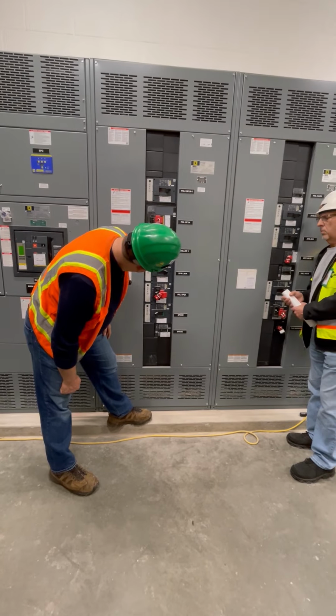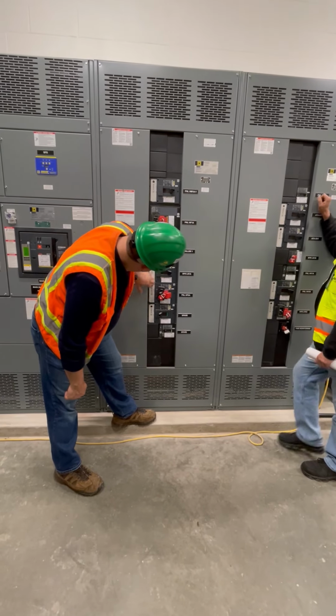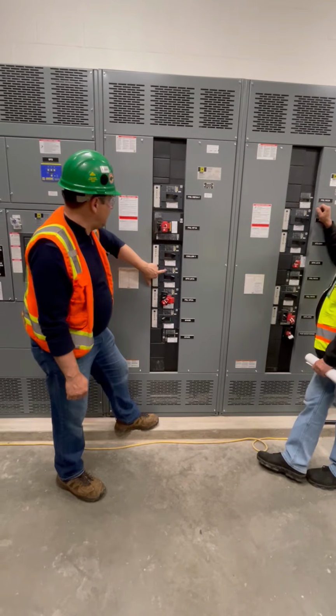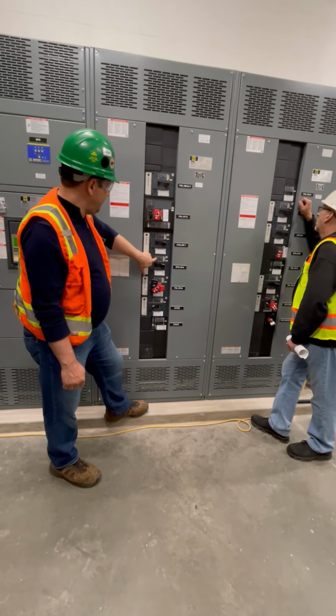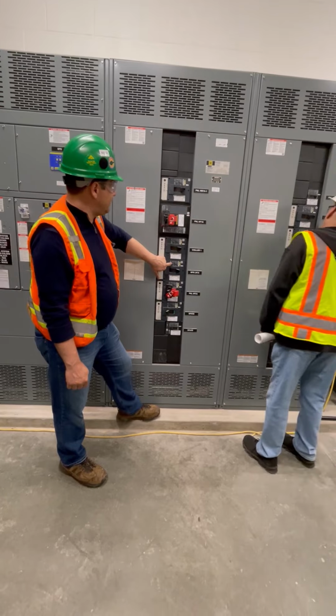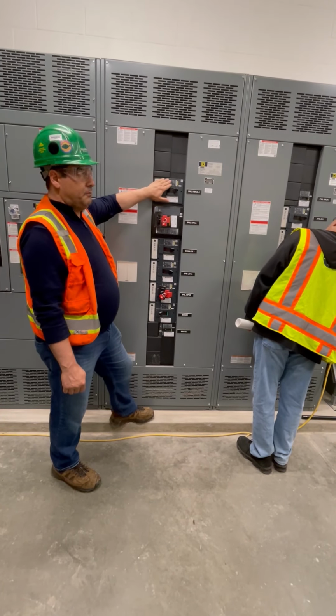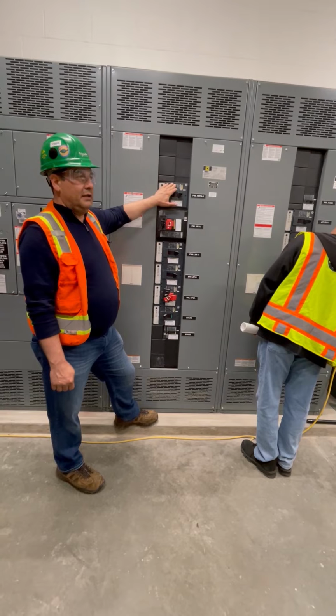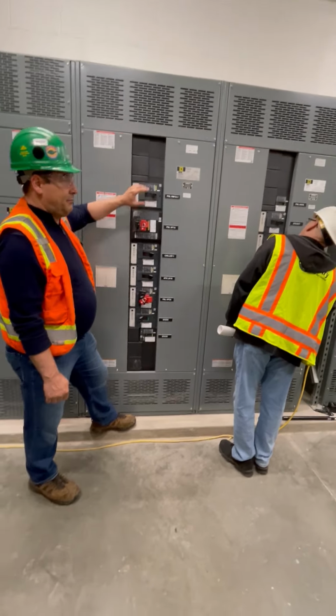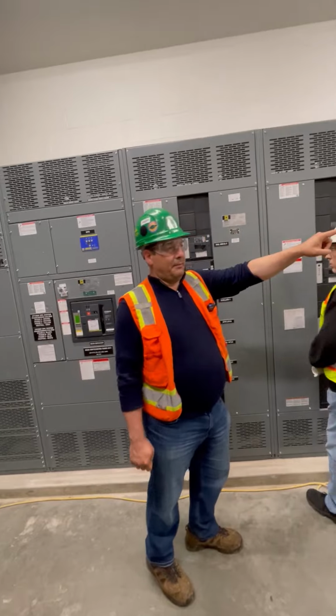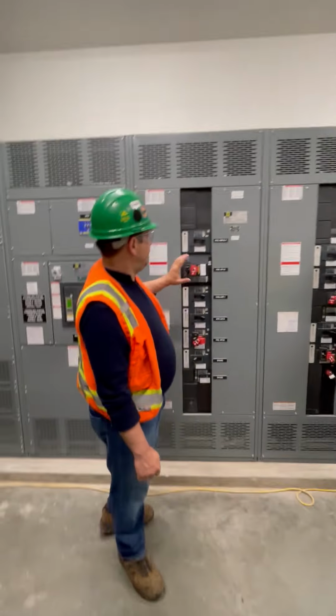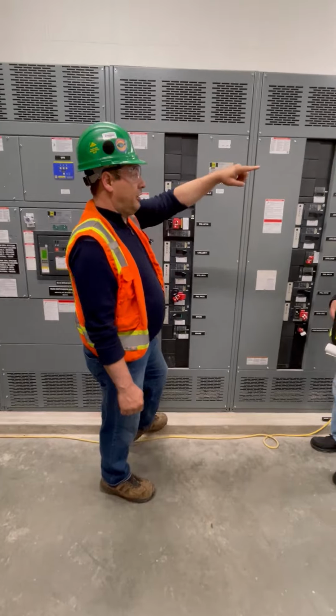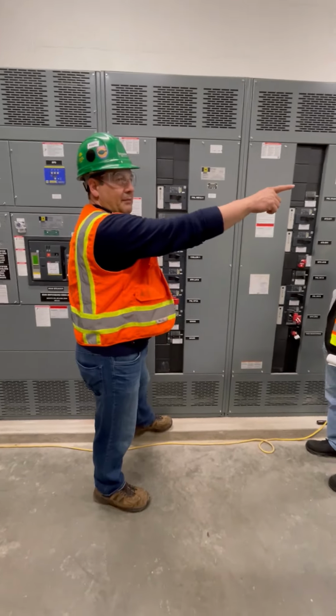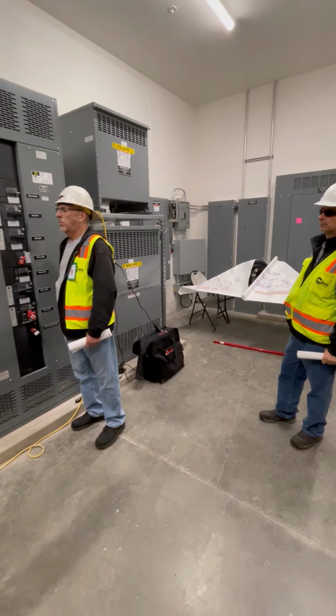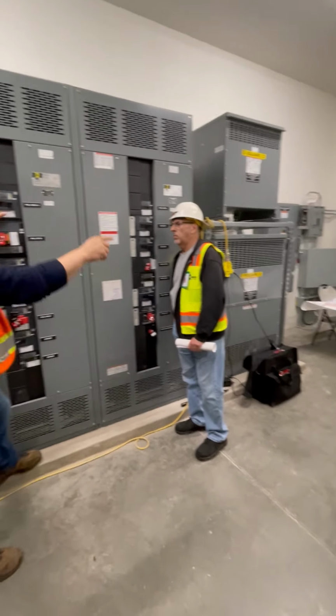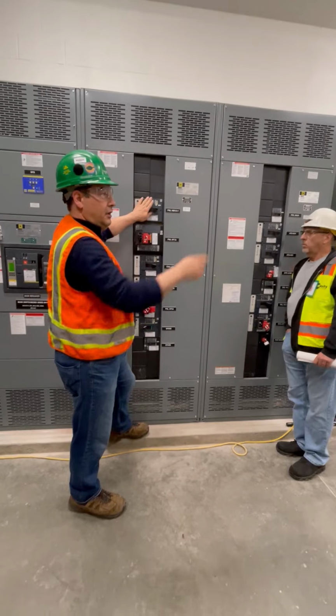These are rated at 65 kA at 480. So that's how they were ordered based on the study that was done. Basically, any breaker that you plug in here has to be 65 kA rated. Now, you find out that these are I-line style breakers. You can take this breaker from here and plug it into that panel, okay? Which is fine, because this breaker is higher fault current rated than that panel.